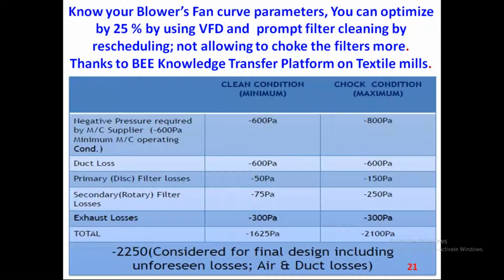The compressed air kg loss from 6 bar to 7 bar is seen, but the Pascal loss from 600 Pascal to 700 or 800 Pascal is not seen by the individual. This is where we have to monitor the Pascal to maintain this, and we can maintain the same blower at 1600 Pascal instead of 2200 Pascal. From 2200 to 1600 means straight away 25% saving is possible in the existing waste collection systems, not only in the textile mill.